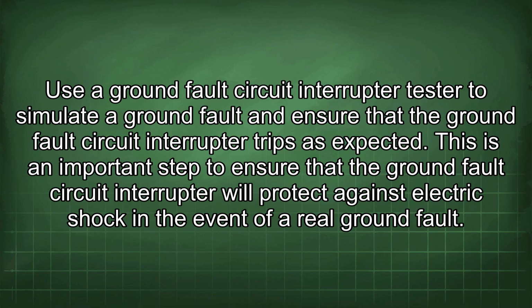Use a ground fault circuit interrupter tester to simulate a ground fault and ensure that the ground fault circuit interrupter trips as expected. This is an important step to ensure that the ground fault circuit interrupter will protect against electric shock in the event of a real ground fault.